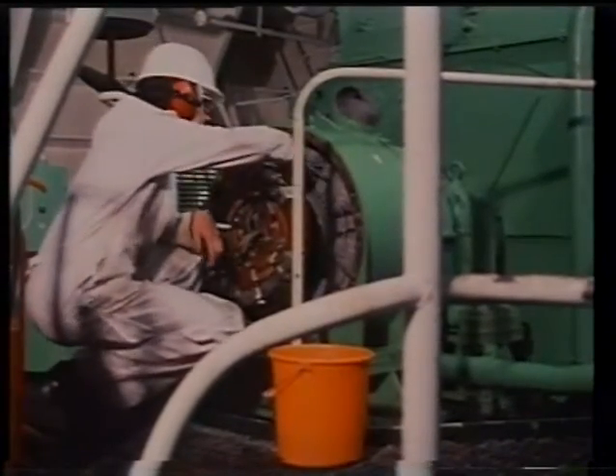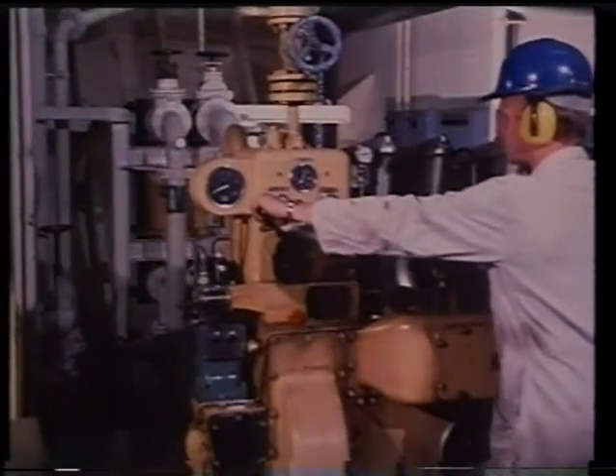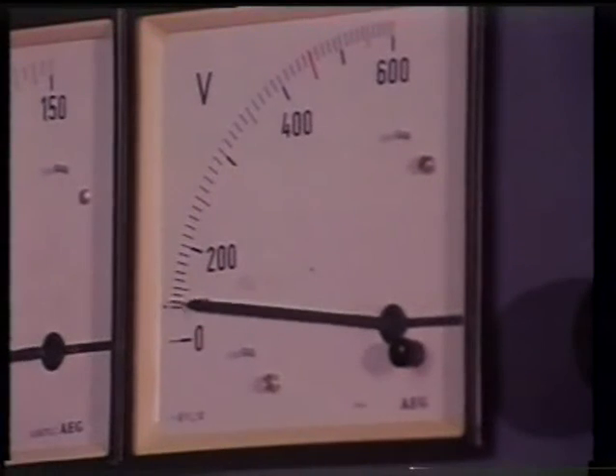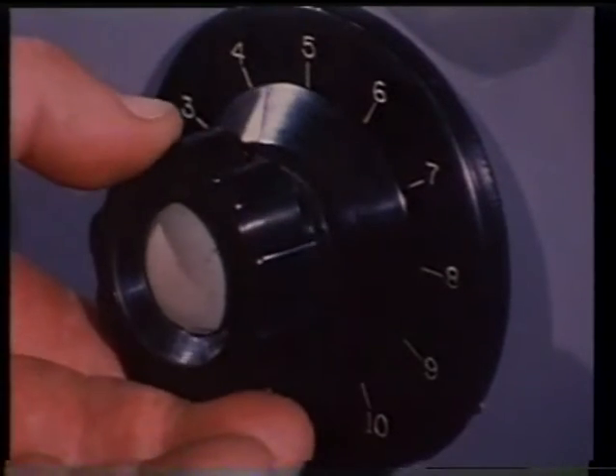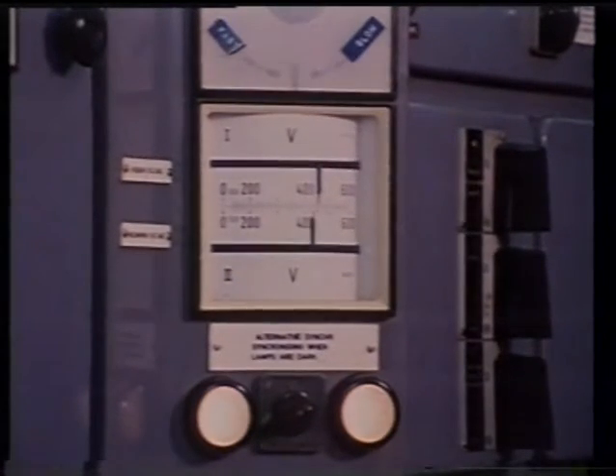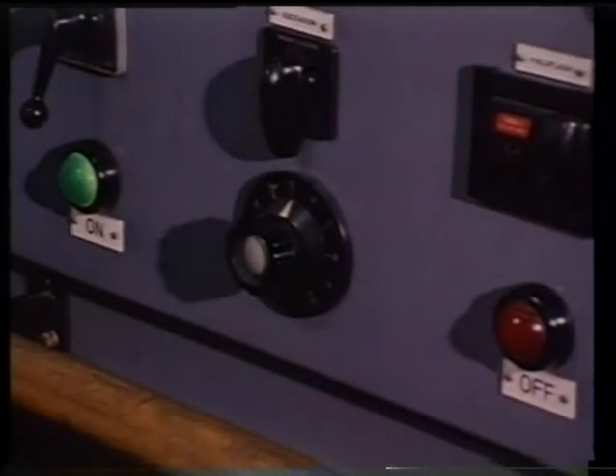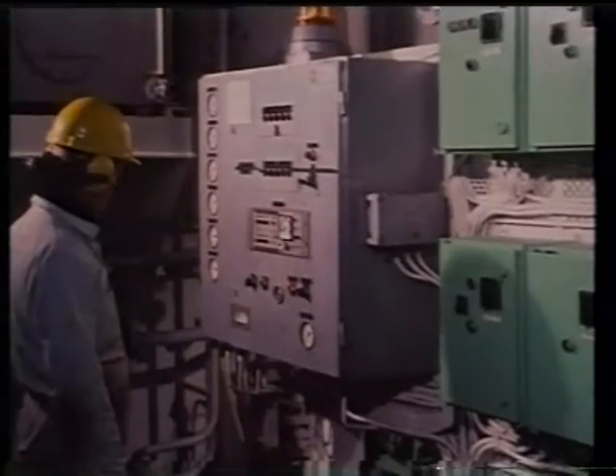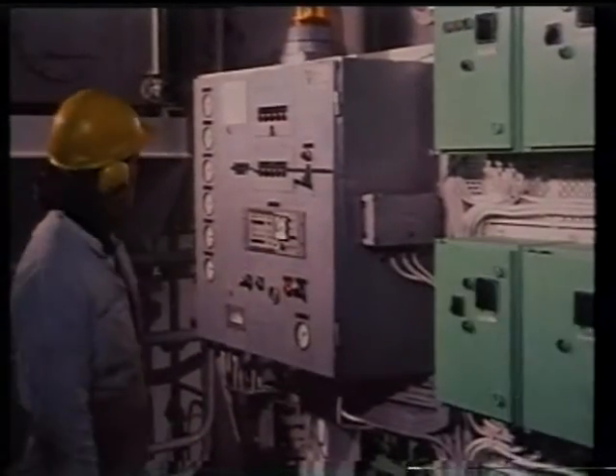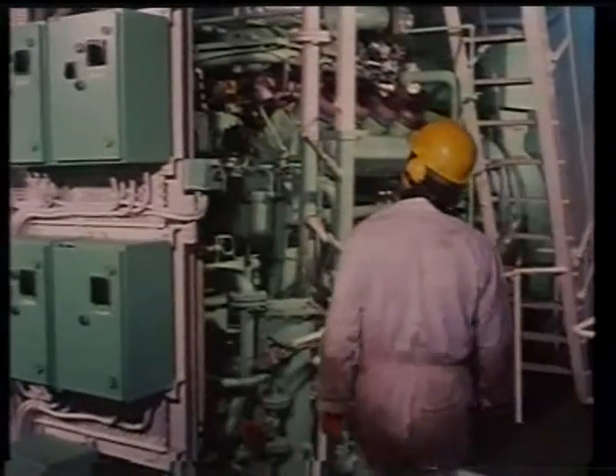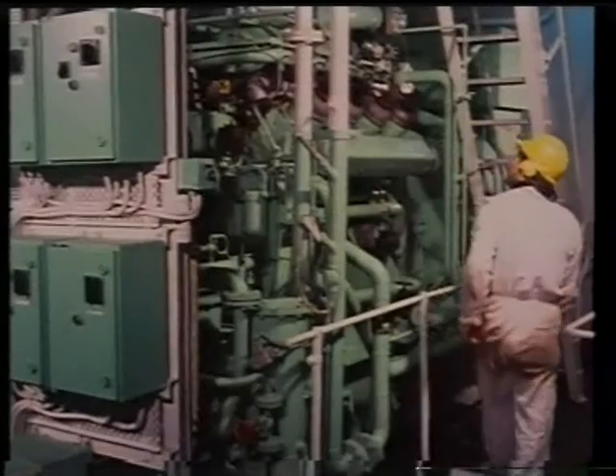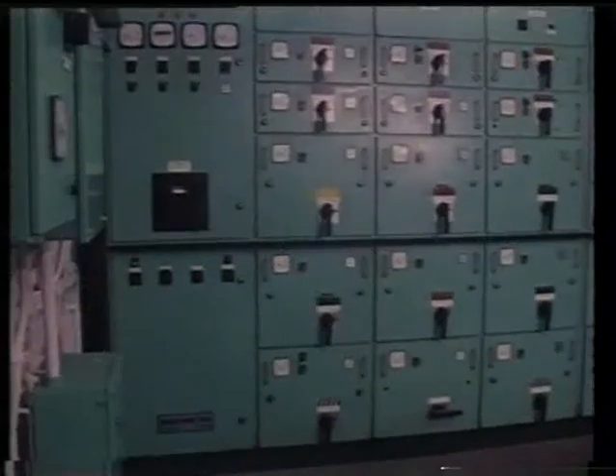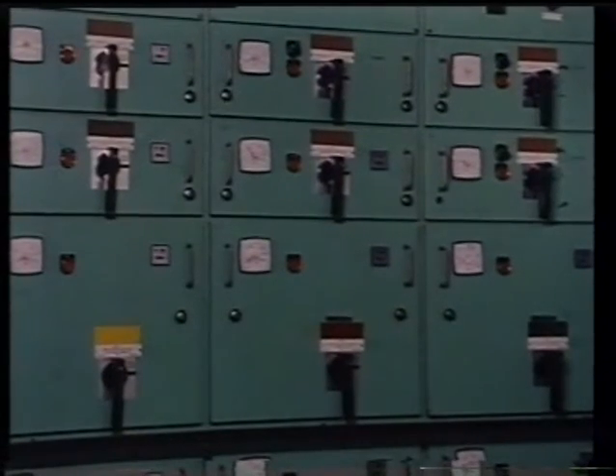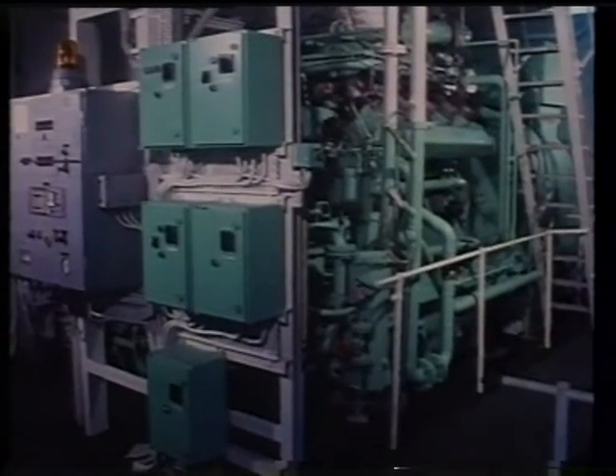Clean all AC generator windings and check your instruments and controls for AC generator synchronizing. The survey will require that the AC generators respond correctly to controls and load changes and that they show a stable operation when running in parallel. Test the automatic startup system for the emergency AC generator, ensuring that the system is operational within the regulation 45 seconds after a mains failure. Connect the emergency AC generator to the switchboard with a load, such as the motor for a firefighting pump. When you're ready to connect the AC generator to the emergency switchboard, do remember that the AC generator breaker cannot be closed until the tie breaker from the main switchboard is opened.